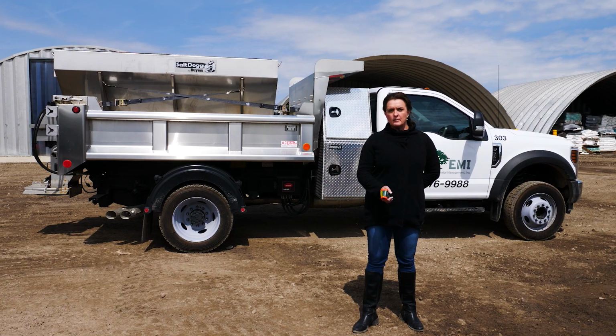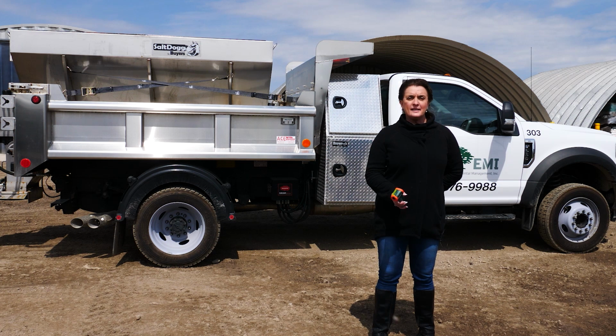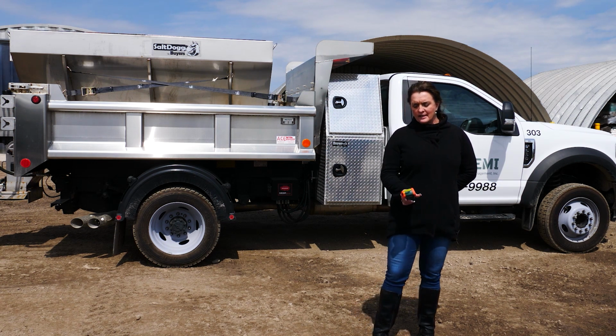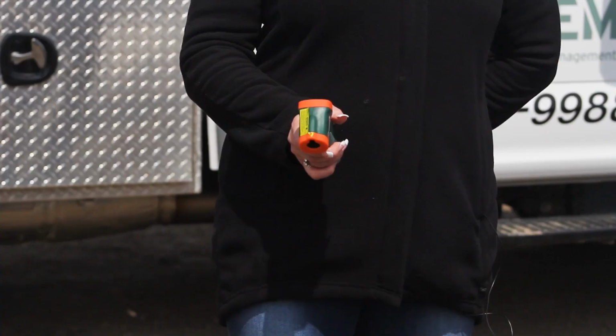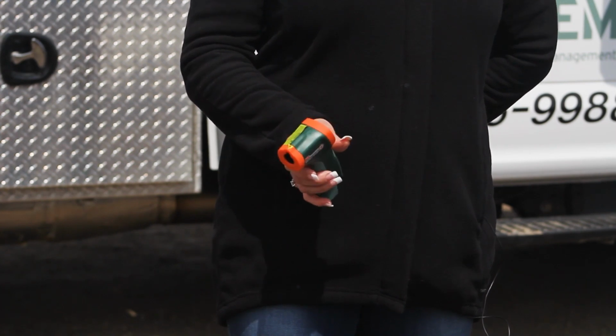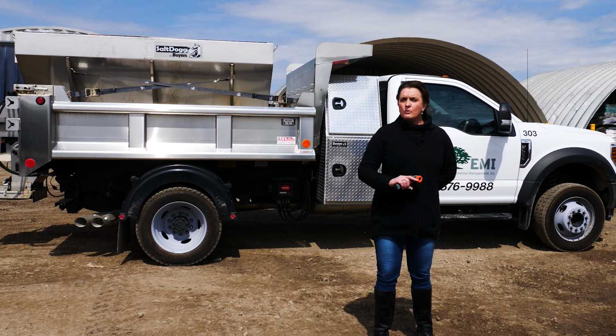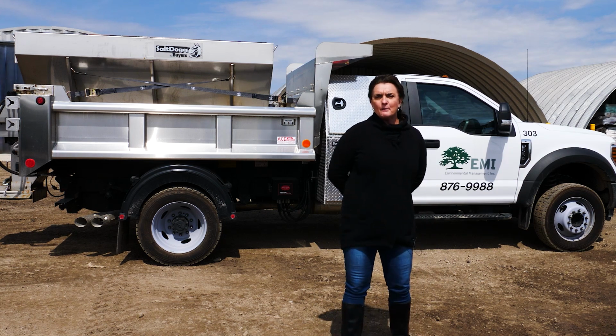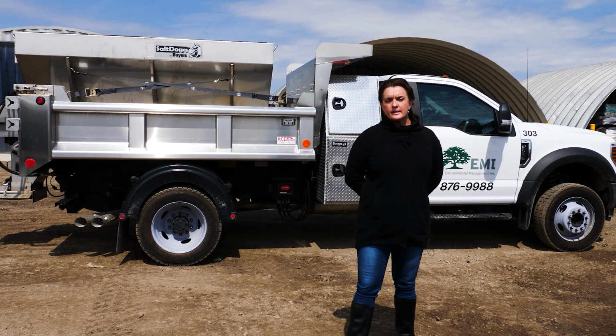Another thing to keep in mind is that a lot of times these types of units will have to acclimate to their environment. So if in the wintertime it's on your truck seat and you choose to use it outside to measure a surface temperature, it typically can take up to 20 minutes for one of these units to acclimate to the outdoors. It's just the limitations of the tool. So make sure when you're using this kind of handheld temperature measuring gun that you know what those limitations are.